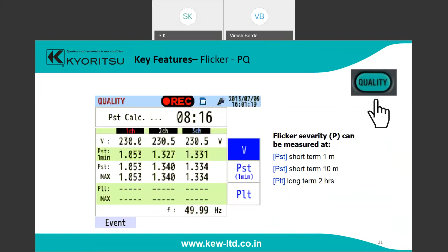This is the flicker display. Push the quality button and you get a direct reading for voltage. If you want to show a short term reading, like 10 minutes, you can customize and select PST, which shows the 10-minute reading. For longer periods like 2 or 3 hours, you can set PLT to see the flicker value over a long time.